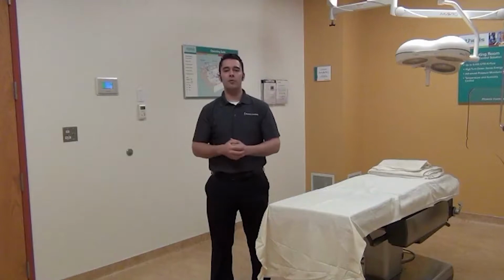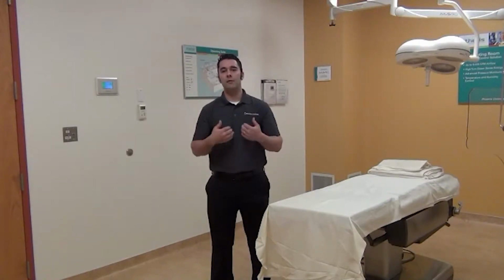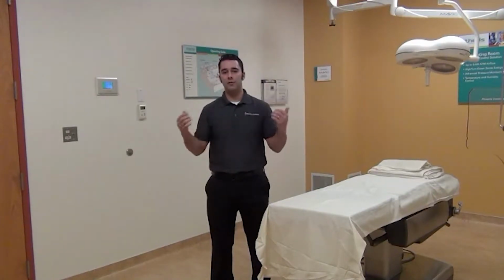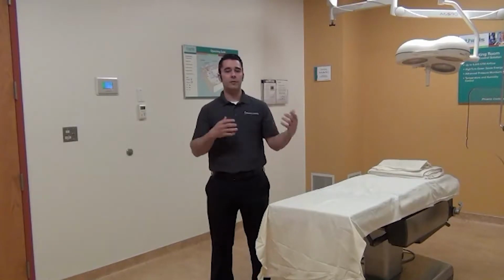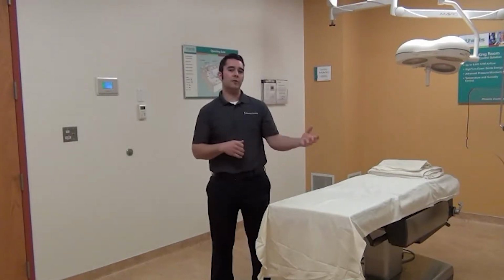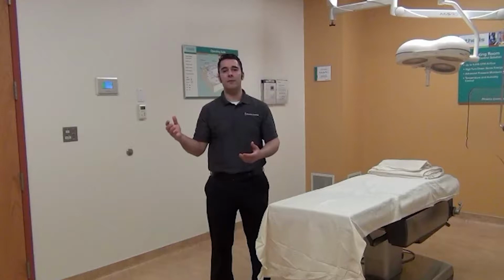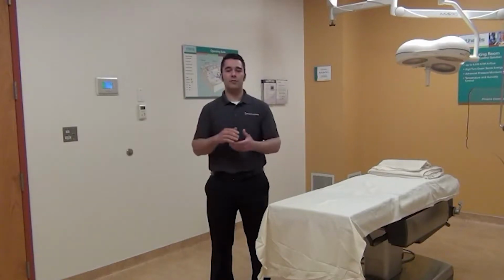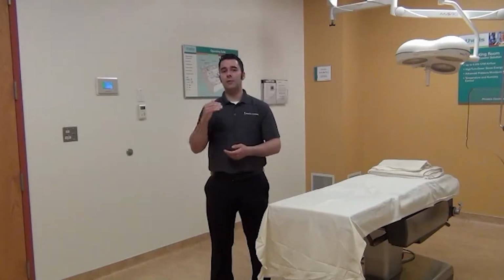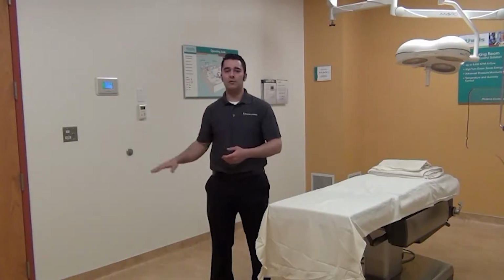And again, what we're trying to show the customer is not only do the Phoenix Controls products have the turn down ratio they want, so in this particular room we can go from about 200 to 1300 CFM on both the supply and general exhaust to make sure that the room can get the air changes it needs, but also make sure that as they transition from occupied to unoccupied, that they guarantee that the pressurization is always going to be constant inside of the space.